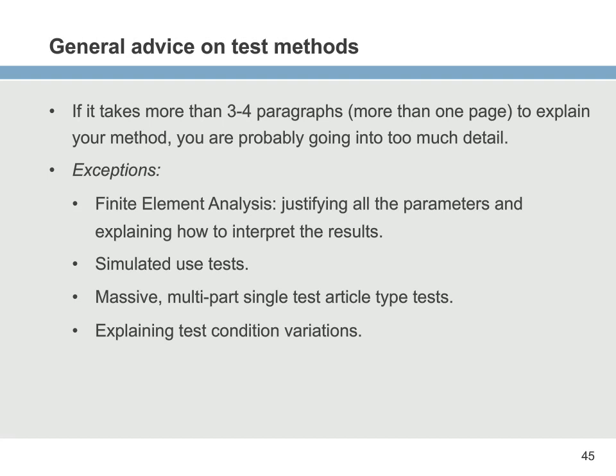I found that when I'm trying to explain finite element analysis testing, it takes quite a while to explain what's happening, to justify the parameters, and explain how to interpret the results. Simulated use tests can be complicated because the instructions for use may have 15 steps, and the test involves replicating every one of those steps, so you've got to explain that we did this with the device, and there's just no way around it.